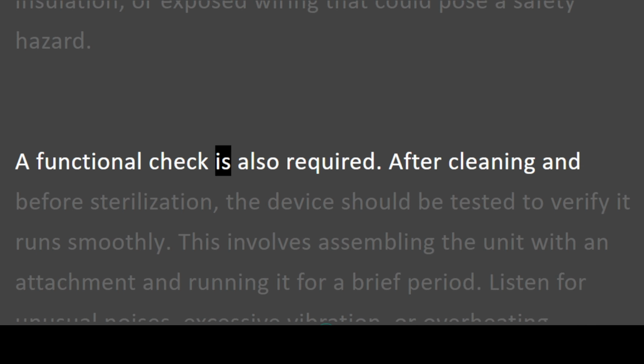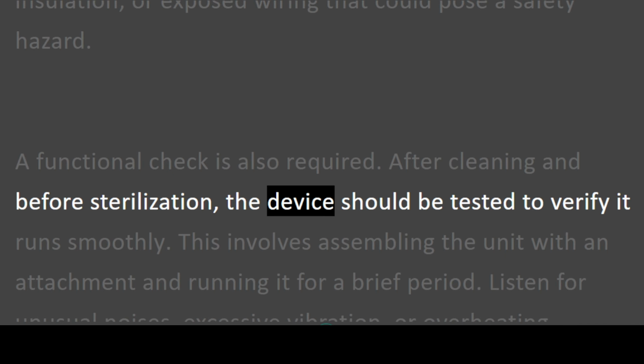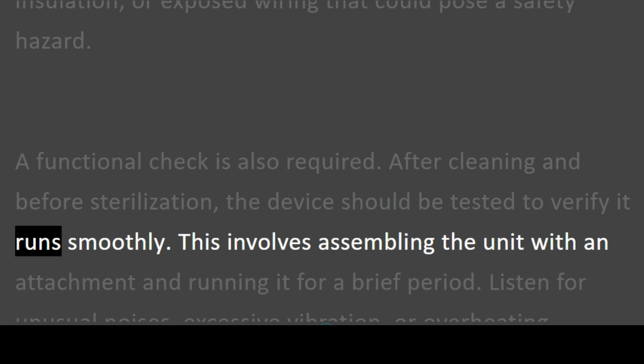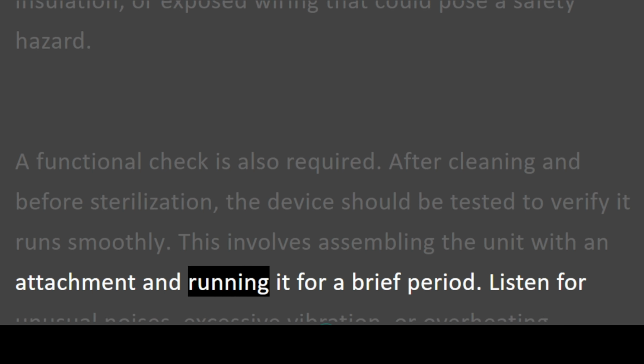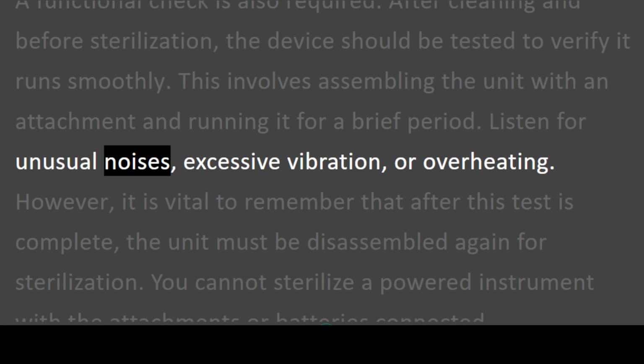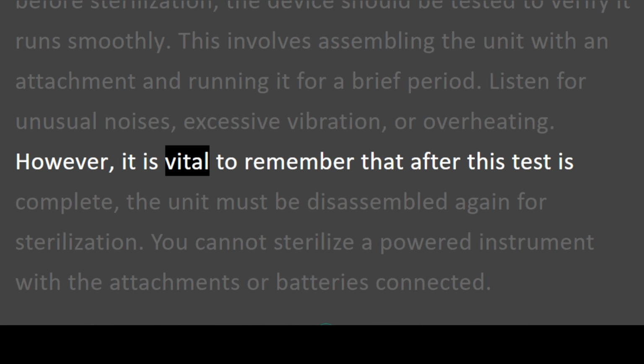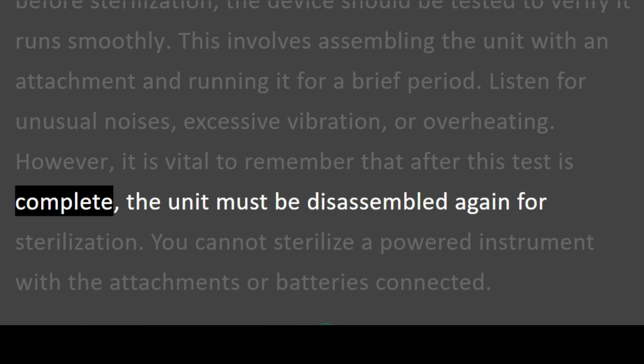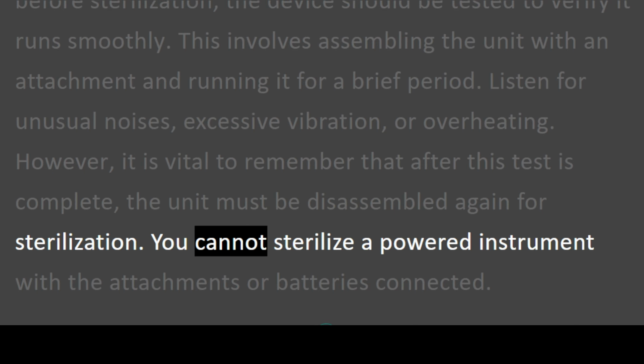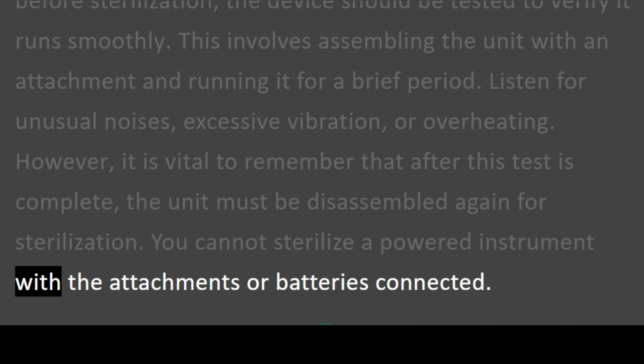A functional check is also required. After cleaning and before sterilization, the device should be tested to verify it runs smoothly. This involves assembling the unit with an attachment and running it for a brief period. Listen for unusual noises, excessive vibration, or overheating. However, it is vital to remember that after this test is complete, the unit must be disassembled again for sterilization. You cannot sterilize a powered instrument with the attachments or batteries connected.